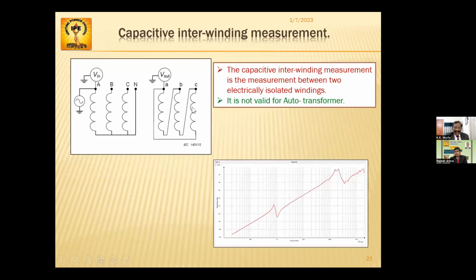This is capacitive measurement between HV and LV. In this, you can see AN is being taken. In this case, A is earth, whereas here also A is earth, and no other earthing is there. But this particular thing is not valid for an auto transformer, because an auto transformer is not magnetically separated. It has a common winding. So capacitive interwinding measurement is a measurement between two electrically isolated windings. So in a conventional transformer you can have this, but not in an auto transformer. That has to be taken care of and kept in mind.